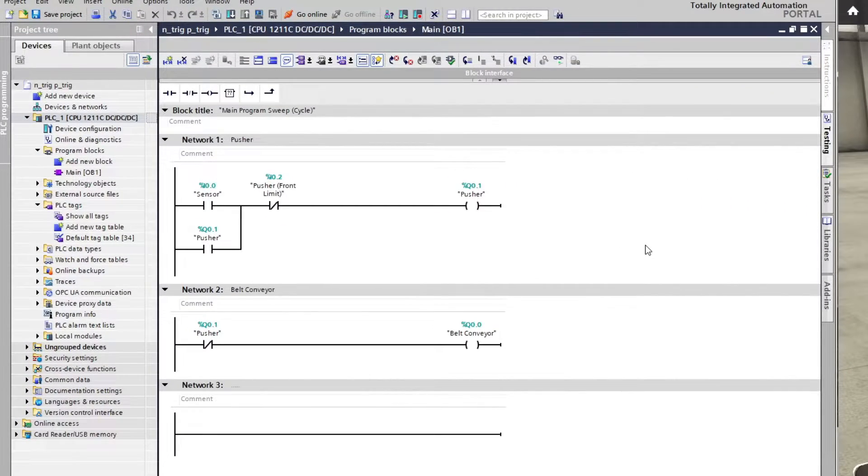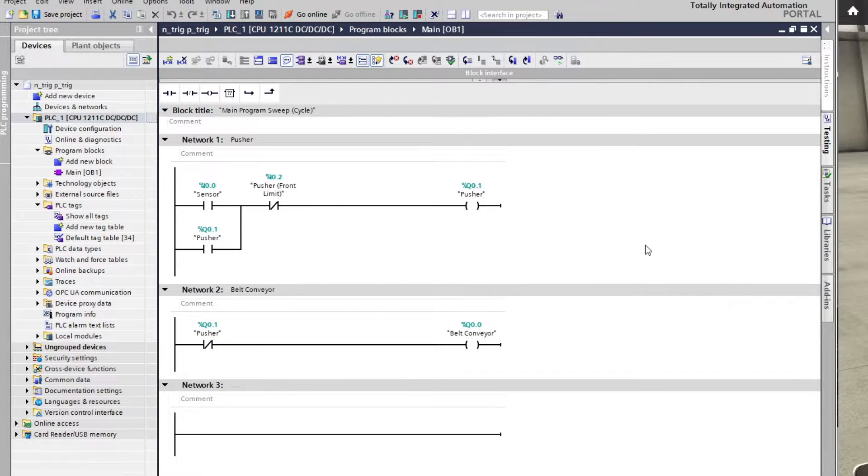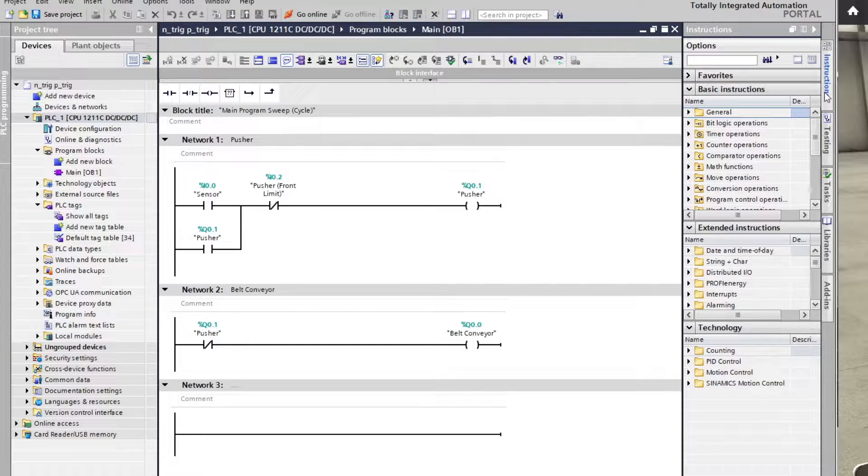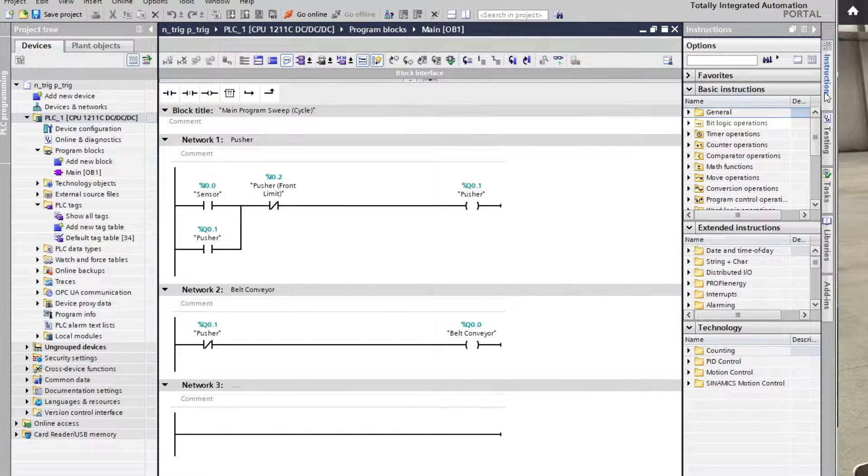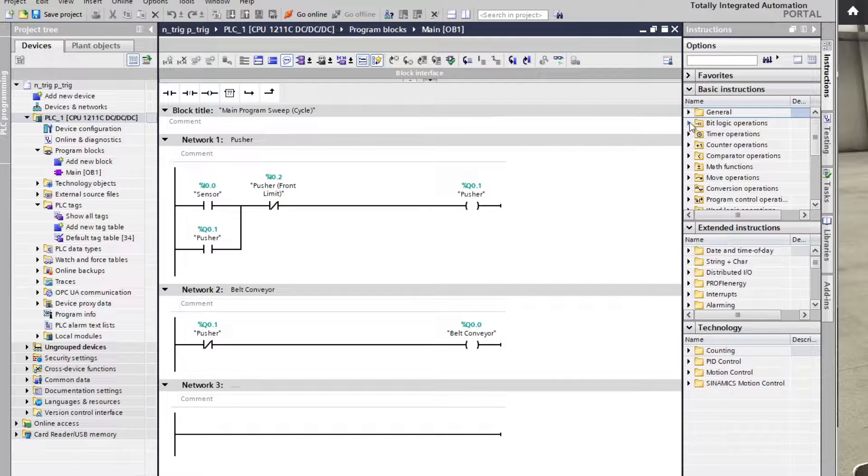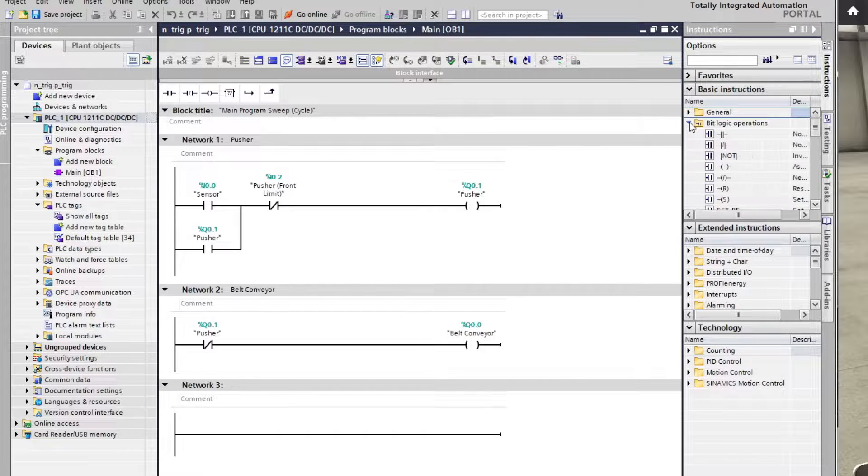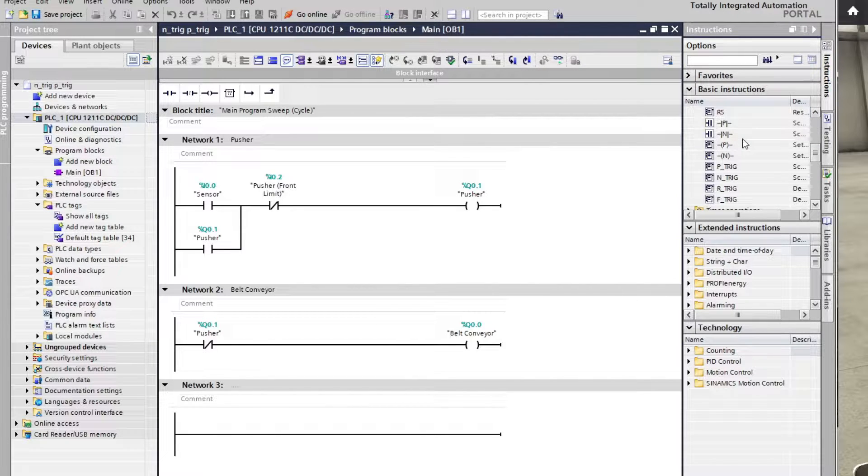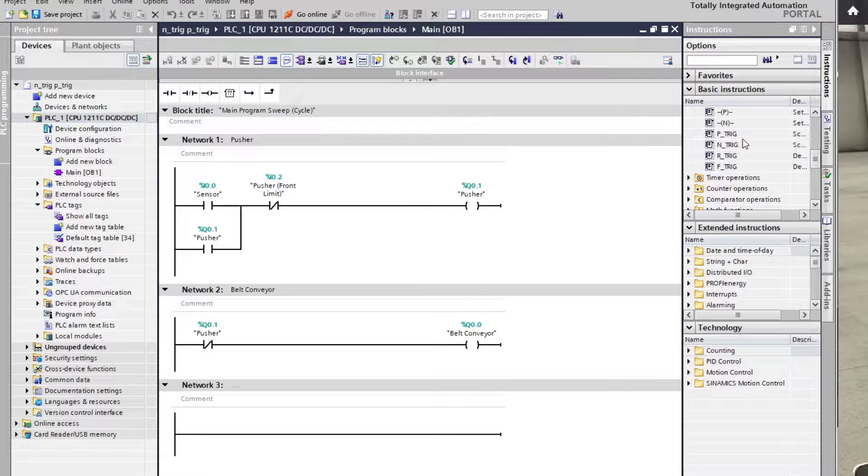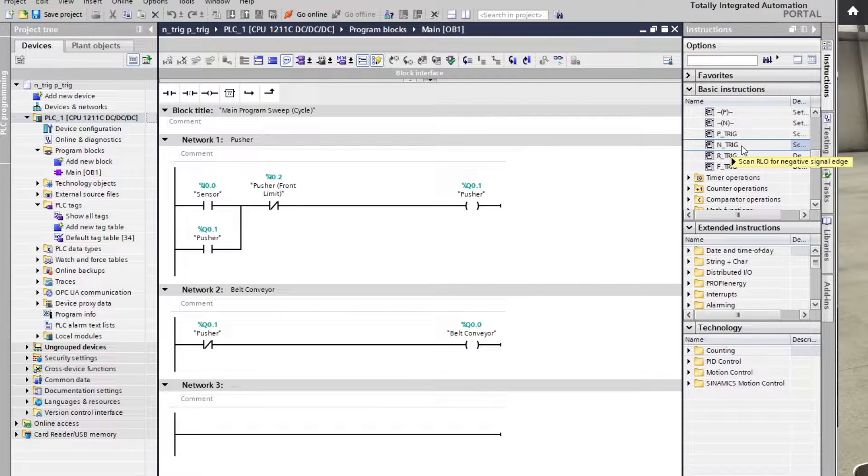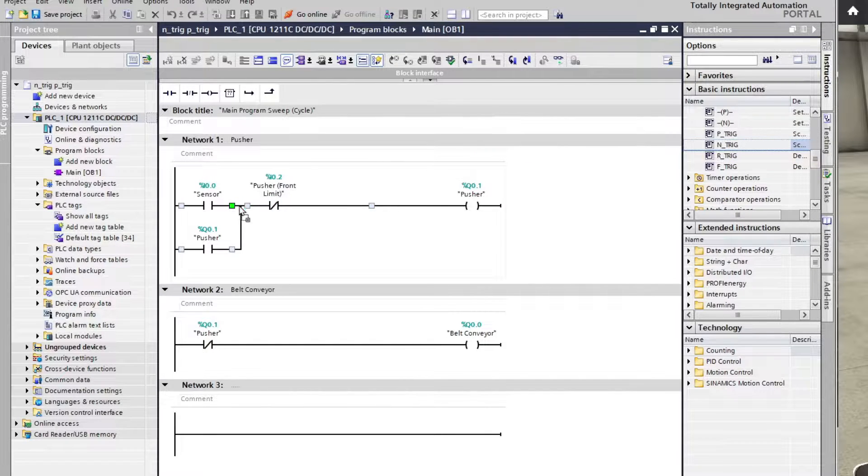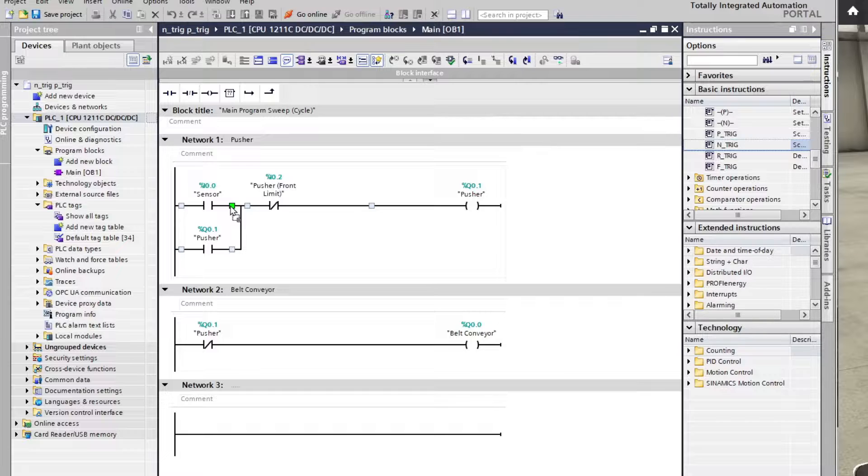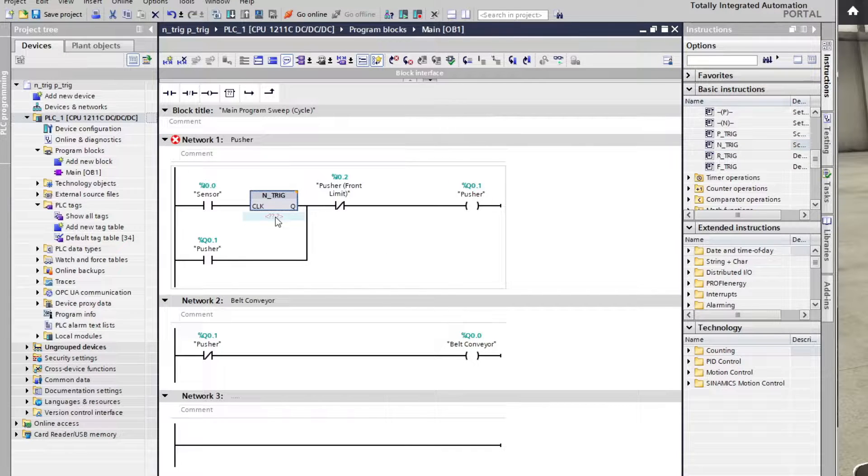To add an N trig function block we need to first open up the Instructions tab. Under the BitLogic Operations tab we can find the N trig function block. Just click it and drag it to the rung. Then we need to declare a BitTag for the block.